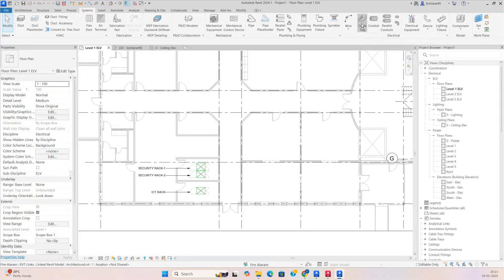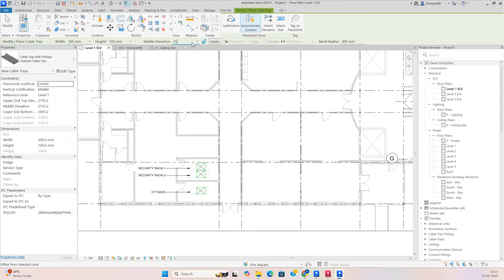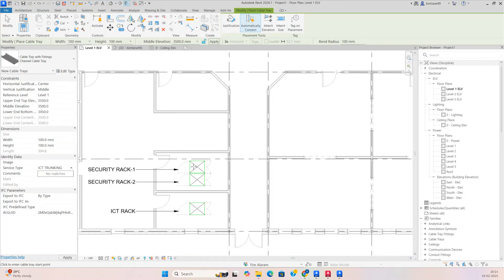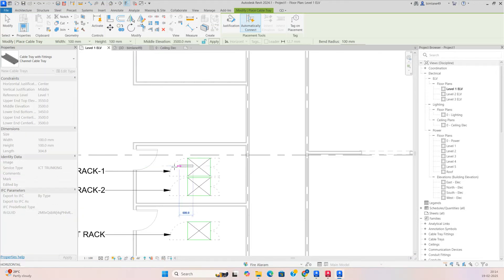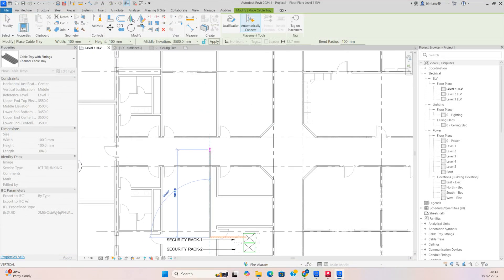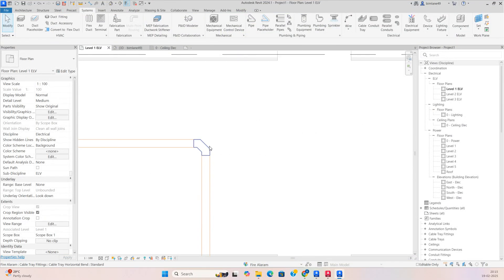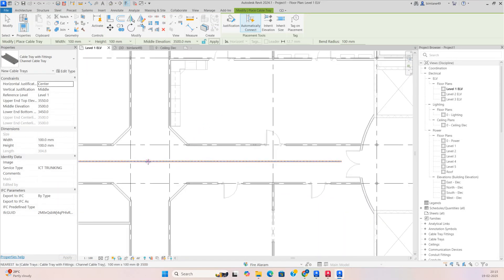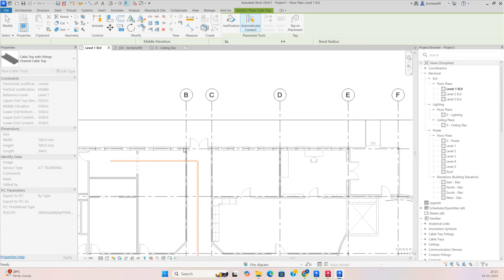Now we can run the cable tray. Go to System, select Cable Trunking, and give the elevation around 2500 or something like that. You can make the trunking 100x100 if needed. Give the service type as ICT Trunking first, then just run the cable trunking from here toward where all the equipment, cameras, and data points are. Press the plus mark and run the cable trunking wherever you require.